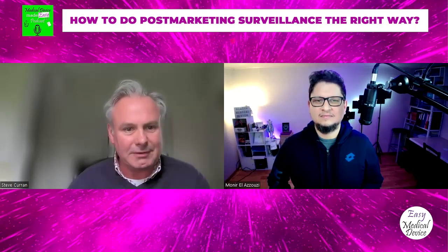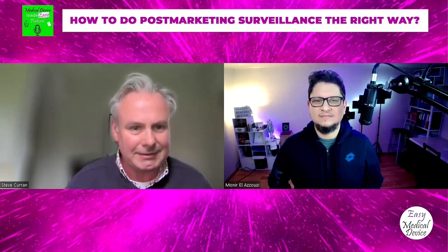with the lower classification devices, maybe the class 2A devices in the EU, sometimes there's a misconception that PMS is all about just customer satisfaction, and the collection of data is not focused on the intended use, on the clinical benefits, on the safety. It's more of a customer satisfaction thing. Is the device being delivered on time? Are there no issues with packaging? And are you happy with your sales guys? And sometimes the feedback is based around that. And there's more emphasis on that, shall we say, than on what it's really all about, and that's the clinical performance, clinical safety. So that's one of the first things that comes out, is the actual data itself.